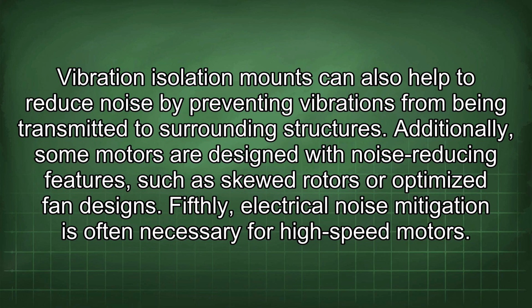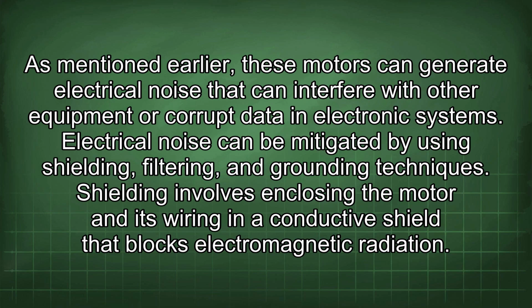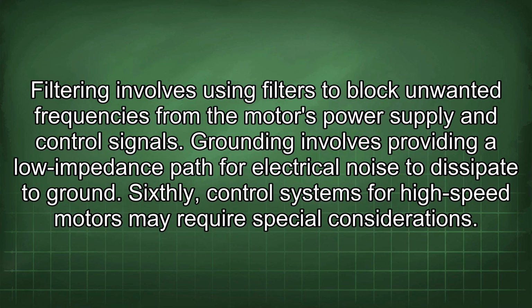Fifthly, electrical noise mitigation is often necessary for high-speed motors. As mentioned earlier, these motors can generate electrical noise that can interfere with other equipment or corrupt data in electronic systems. Electrical noise can be mitigated by using shielding, filtering, and grounding techniques. Shielding involves enclosing the motor and its wiring in a conductive shield that blocks electromagnetic radiation. Filtering involves using filters to block unwanted frequencies from the motor's power supply and control signals. Grounding involves providing a low-impedance path for electrical noise to dissipate to ground.